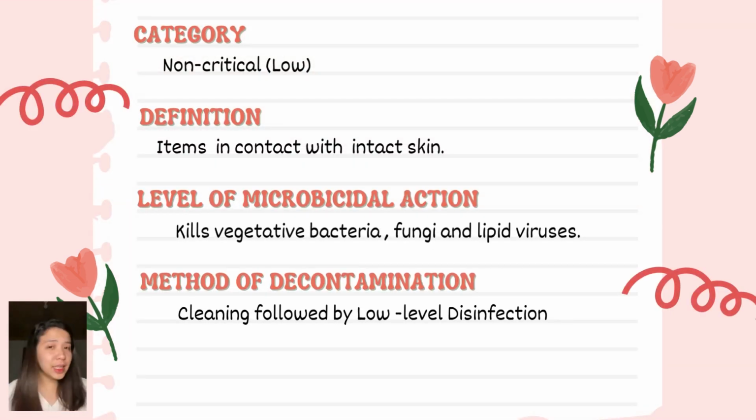And for the last category, which is the non-critical or low category, it covers items in contact with intact skin. It kills vegetative bacteria, fungi, and lipid viruses. The method is cleaning followed by low-level disinfection. In some cases, cleaning alone is acceptable.